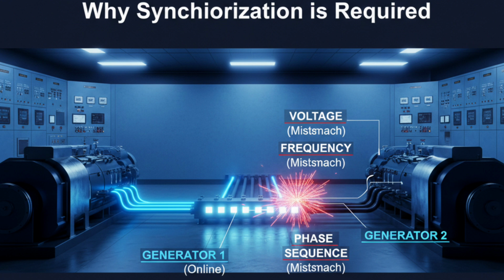Why synchronization is required? Let us first understand why synchronization is necessary. Imagine one generator is already connected to the main busbar and supplying power. Now we start another generator. If we directly close its breaker without matching voltage, frequency, and phase, there will be a huge current surge. This sudden mismatch can cause breaker tripping, reverse power, generator damage, shaft stress, and sometimes complete blackout. Synchronization ensures both generators are electrically identical before connection. That means voltage must be equal, frequency must be equal, phase sequence must be same, phase angle must match exactly. Only when these conditions are satisfied, we close the breaker. This prevents shock, protects equipment, and ensures smooth load transfer. Synchronization is not just a procedure, it is a safety requirement.